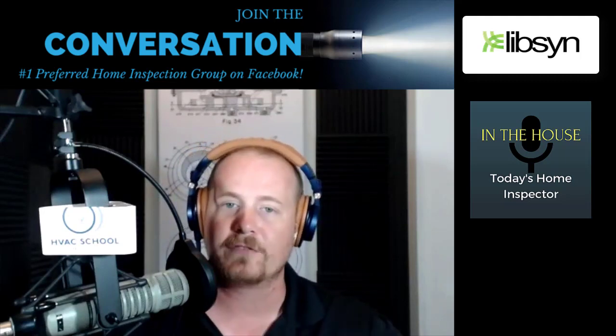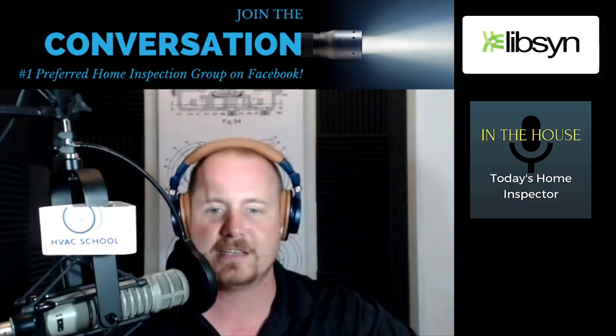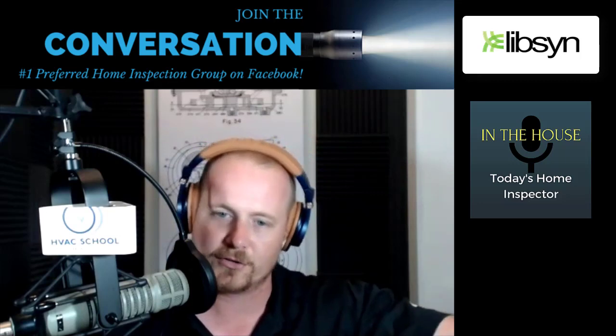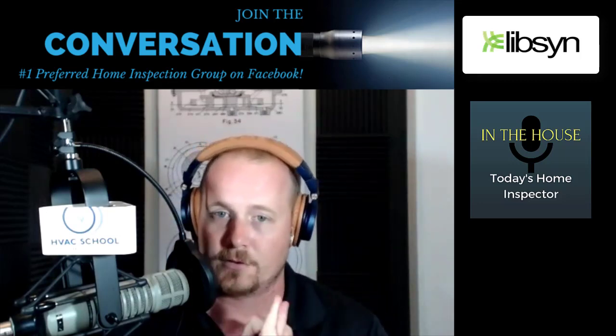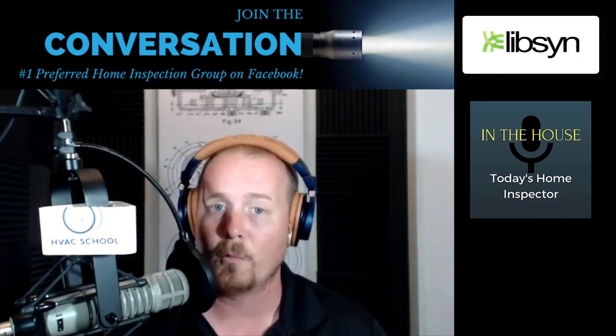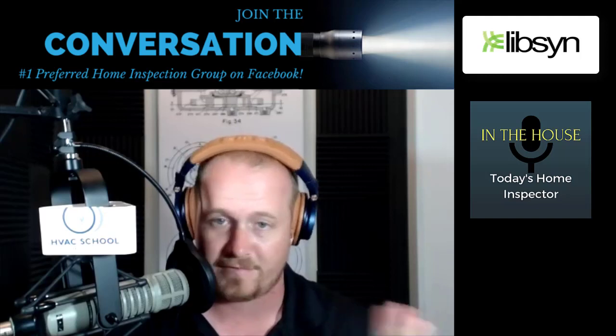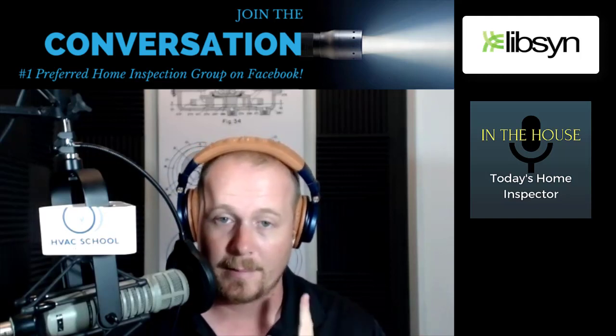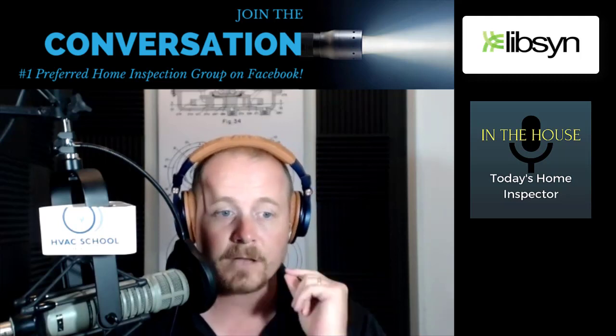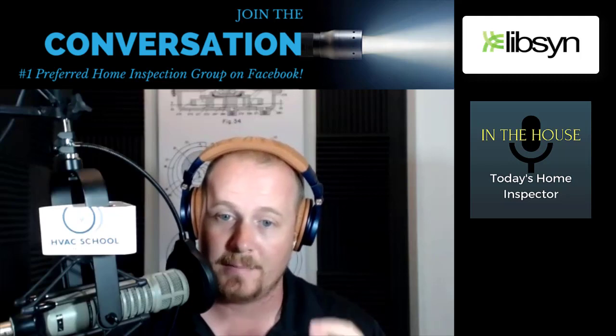So if you want to be the Mac Daddy home inspector, the home inspector that every HVAC contractor will back and cheer as you go through the streets with the ticker tape parade, here's what I would request that you have. A dry bulb thermometer that you can use in your duct. You can buy them at Walmart for $12. I mean, this is just a quick-read cooking thermometer, nothing fancy. Something to measure relative humidity accurately. Now, I'm going to suggest a tool because it's inexpensive and it's highly versatile. It's called the 605i by Testo.